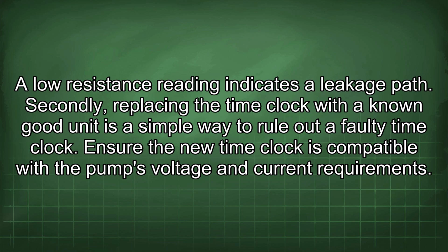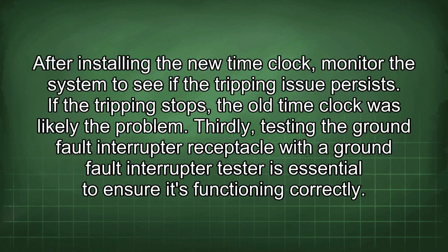Secondly, replacing the time clock with a known good unit is a simple way to rule out a faulty time clock. Ensure the new time clock is compatible with the pump's voltage and current requirements. After installing the new time clock, monitor the system to see if the tripping issue persists. If the tripping stops, the old time clock was likely the problem.